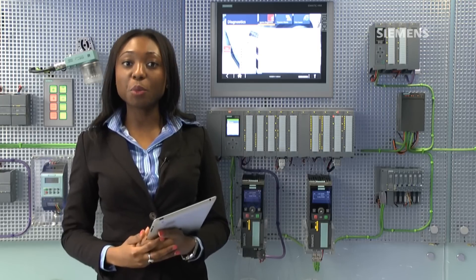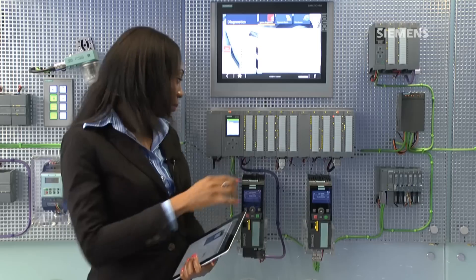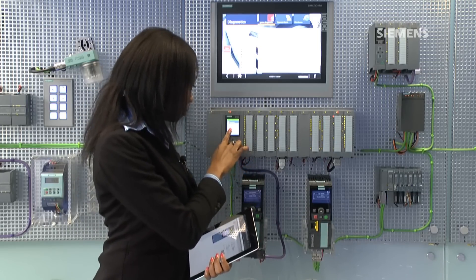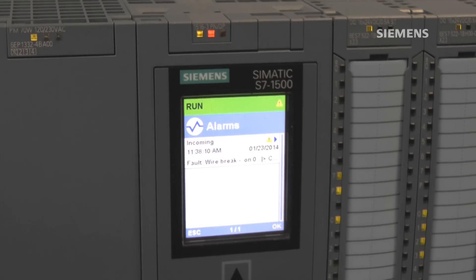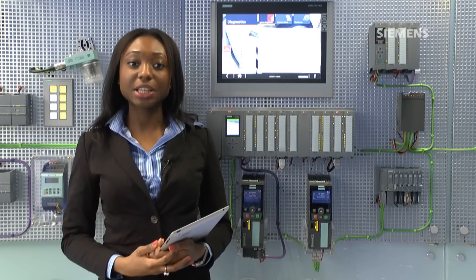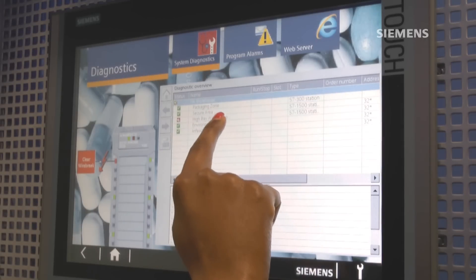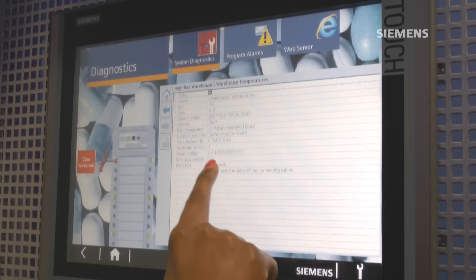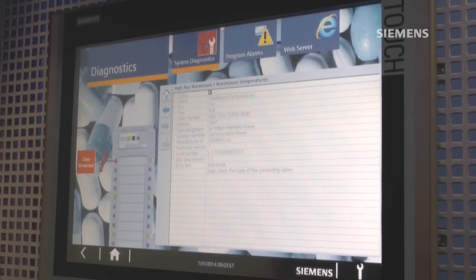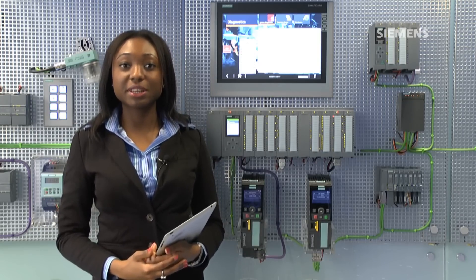The CPU display provides a plain text alarm on where there is a fault using symbolic names defined in the code. This same information is also available to view on the HMI as shown on the diagnostics viewer. And that same message can be seen on the CPU's web server too.